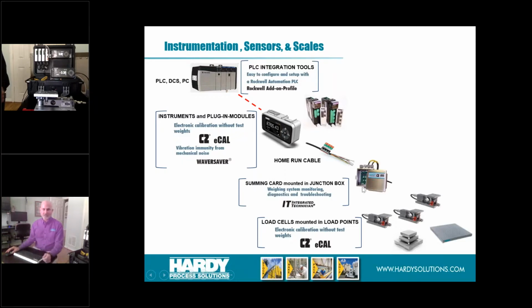So let's say you've seen this demonstration, you like it, and you want these features, but you've got a lot of scales out there and want to know your migration path. Just by changing out the controller, you get any of the Rockwell add-on profiles, and you also have WaverSaver in the controller itself. Adding the home run cable and junction box, you now get the integrated technician. That's your migration path: start with the controller, add the junction box, and later, as your load cells fail, replace those too.